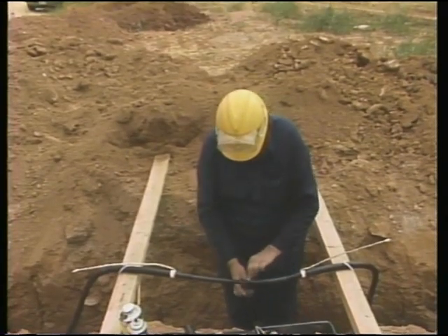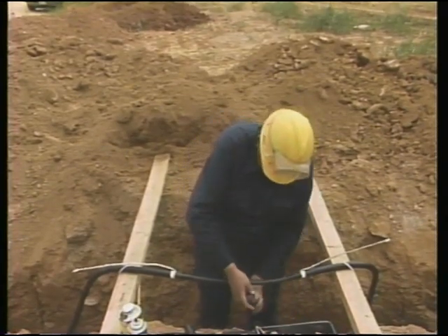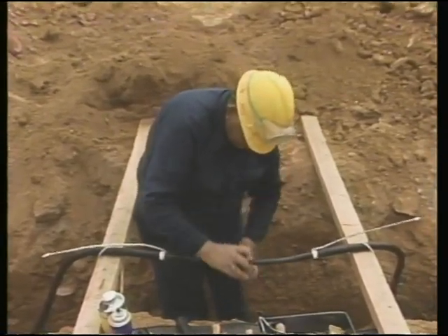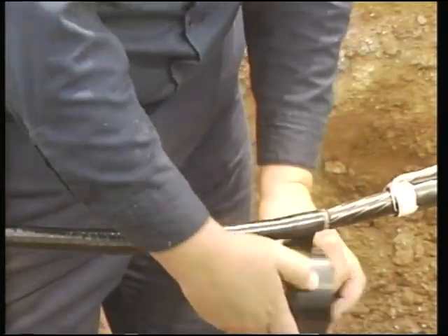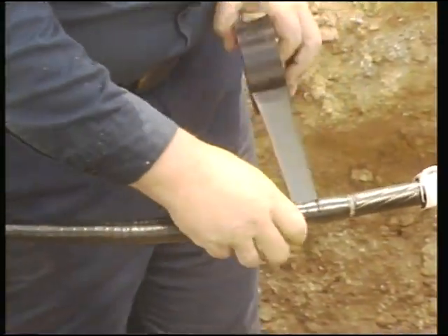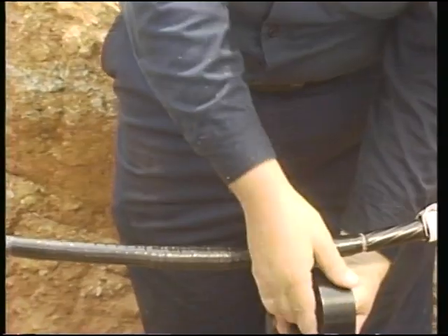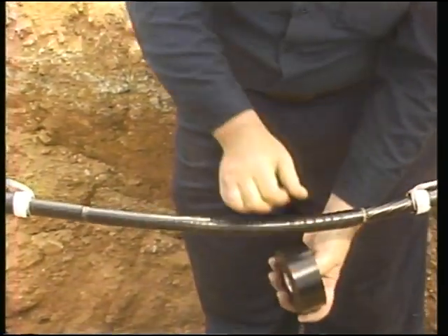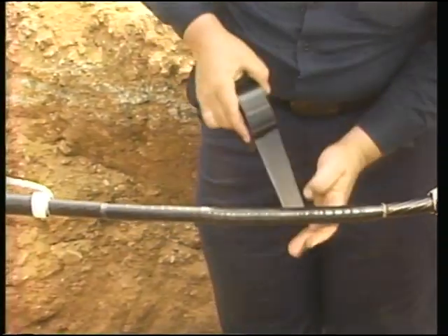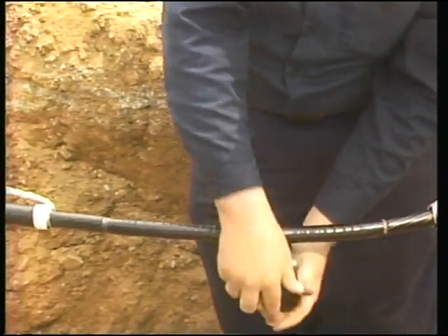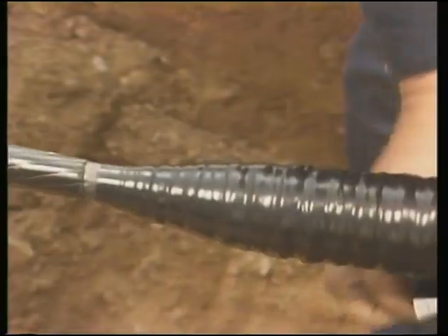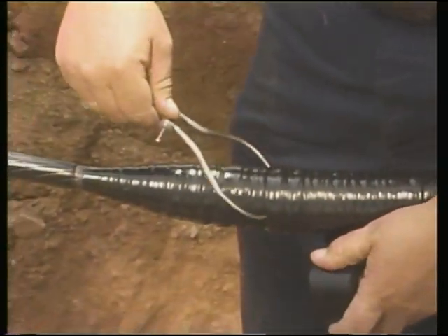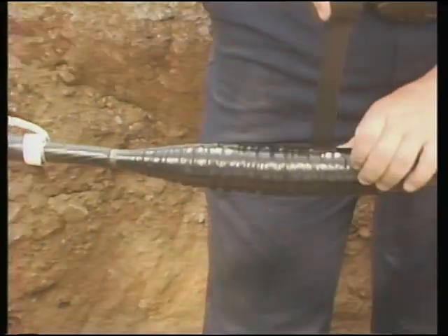Beginning on the connector, the workman wraps half-lap layers, taping over the connector and all of the exposed cable insulation. As the tape is wrapped, it is also stretched to maintain a tight, uniform layer. The tape should be stretched according to the splicing instructions, and even tension should be applied to get a uniform tape density and thickness. Now he'll wrap the tape over the splice until the splice diameter is at the thickness required by the splicing instructions.